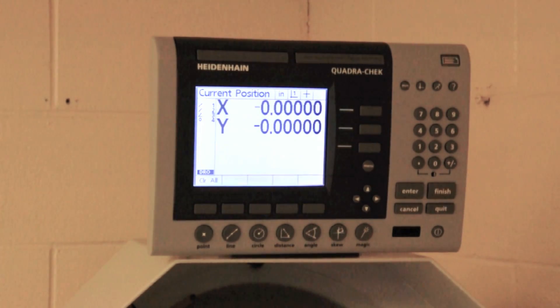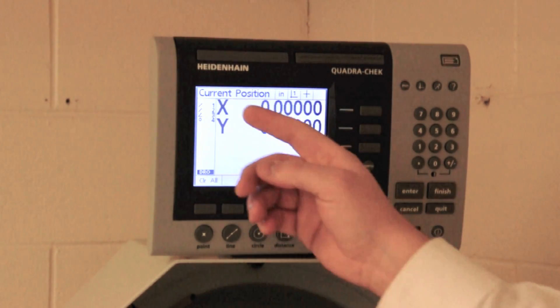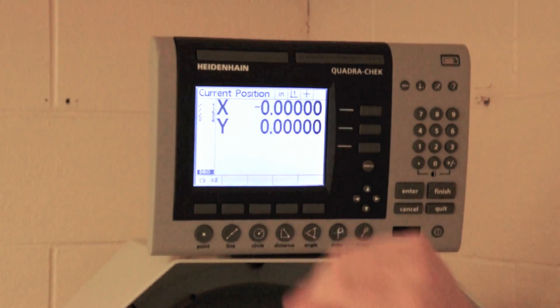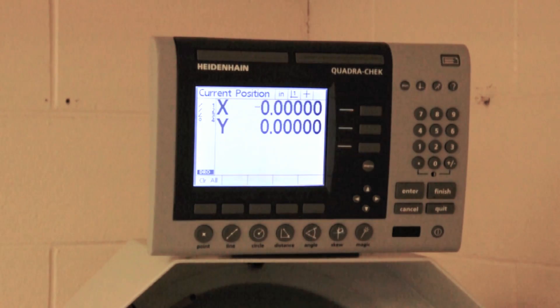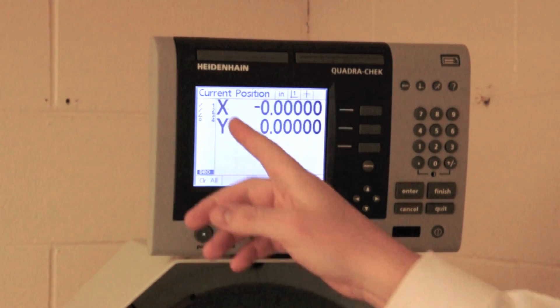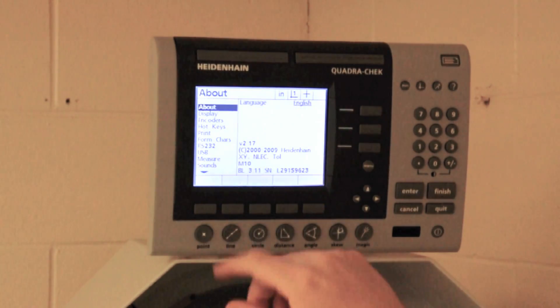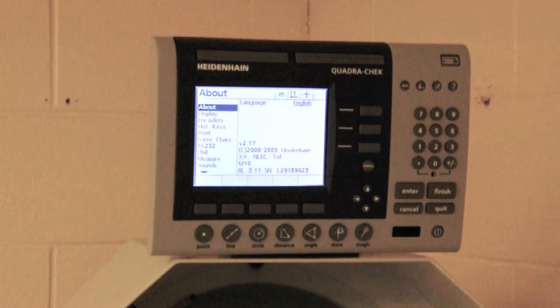On the Heidenhain QuadraCheck display, the previously taken measurements are displayed along the left here, while the front and center are the current X and Y position. And at any time, the previously taken readings can be output through either RS-232 or USB connections.